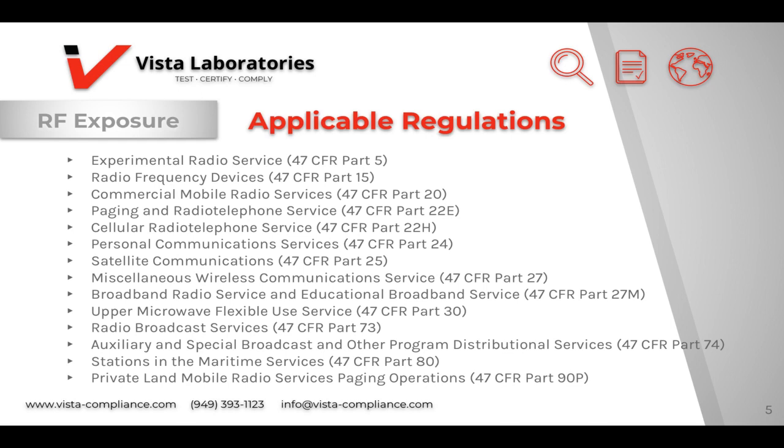Here is a list of rule parts where a routine RF exposure evaluation is mandatory for equipment, which means basically for portable devices, including SAR measurement. These are the rule parts where SAR measurement may be required to show compliance for the different operating configurations of the device, different exposure conditions, and different accessories that the device may come with.